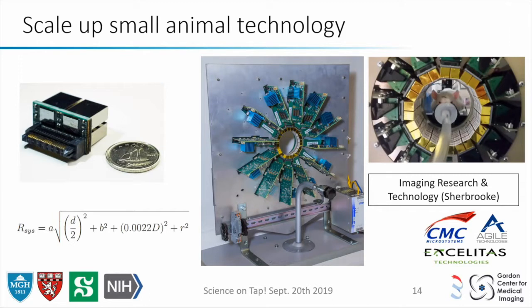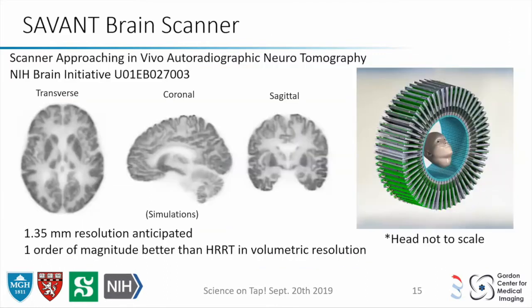The reason this approach works well is that these are APDs — old technology, but with one-to-one coupling, meaning the decoding factor is zero. You don't have to shrink your crystals as much to get high resolution, which matters because very small crystals are harder to manufacture, cost more, and have more losses. Simulations show about 1.35 millimeter resolution in the center of the field of view — one order of magnitude better in volumetric resolution compared to the HRRT. We received funding last year to build this scanner over five years.